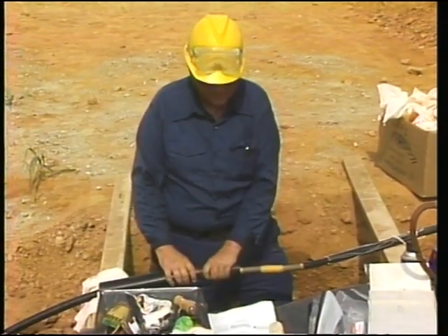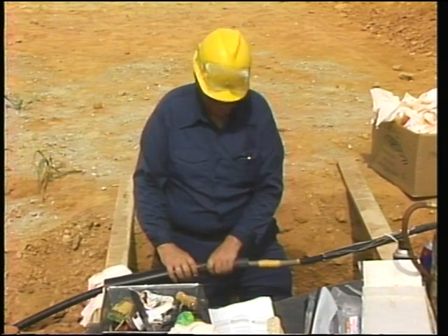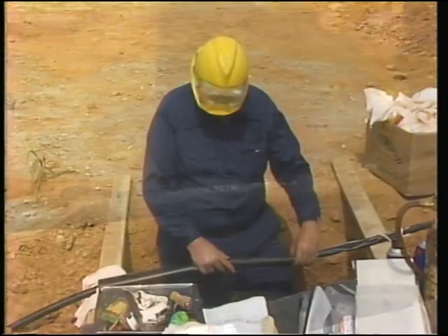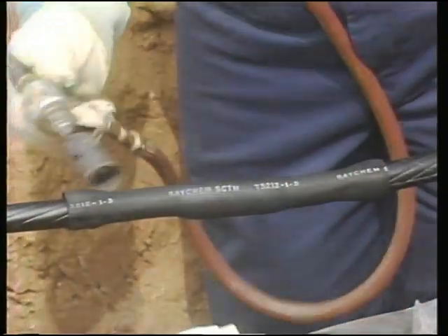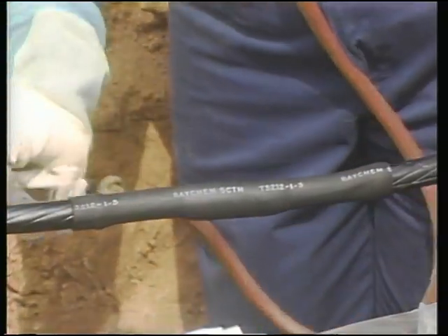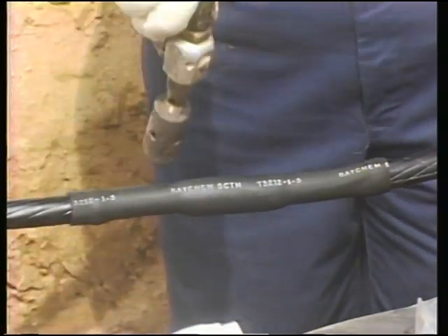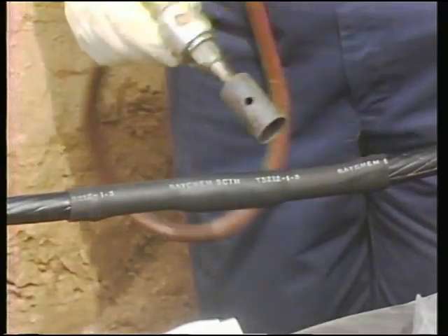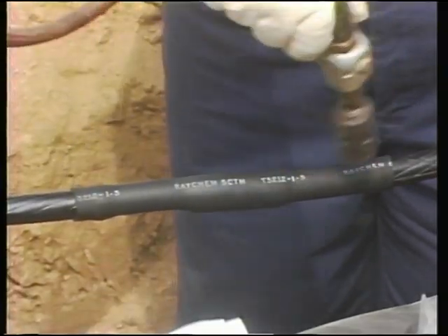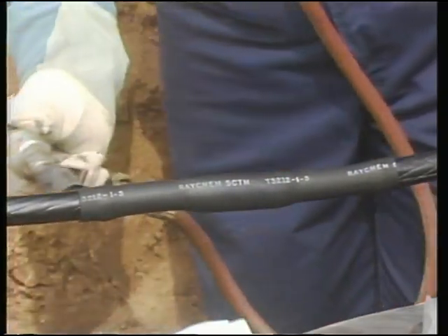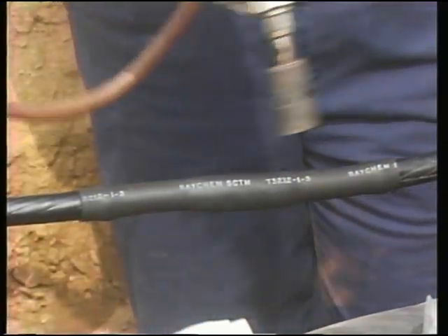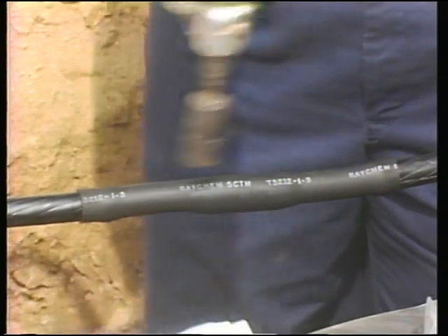Now, after the putty is applied, the smallest diameter tube, which is the stress control tube, is centered over the conductor splice. Using an approved heat source, in this case a torch, the workman starts the heat shrink at the center of the splice and works outward to both ends. The heat should be applied with a brushing motion. This helps to make sure the heat shrink material is not scorched or blistered. You'll also want to make sure that the direct flame of the torch does not contact the cable's semiconductive material so that it is not damaged.